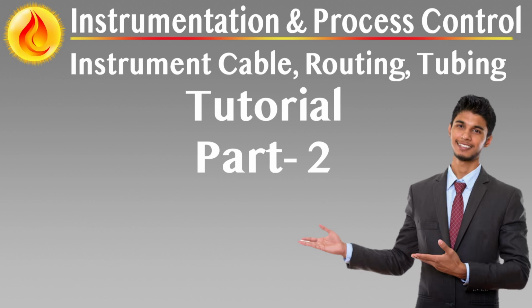Junction box engineering for accessibility and protection. Junction boxes serve as key interface points between field signal cables and multi-core instrumentation cabling. Their placement must optimize proximity to served instruments, generally within 15 to 20 meters, while ensuring location in low fire risk and electrically safe zones, or certified Zone 2 hazardous areas as required. Boxes should be constructed of stainless steel for field durability and fully equipped with mounting rails, terminal blocks, drain plugs, and gland plates. All cable entries must use bottom-positioned metallic glands to prevent moisture ingress. Cables entering laterally must be routed downward before entering, maintaining a drip loop.